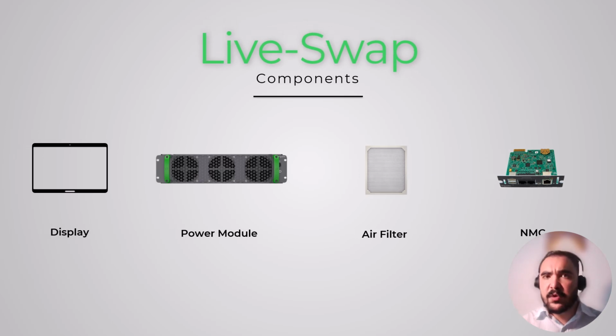Those are the 4 live swap components that you can replace while the UPS is in operation. Any other components, you will need to bypass the UPS to replace them. We have first the display, and this is, by the way, the first 10-inch display used by Schneider Electric. All of the previous displays were 7 inches. We have the 125 kilowatt power module. We have the air filter and network management card.